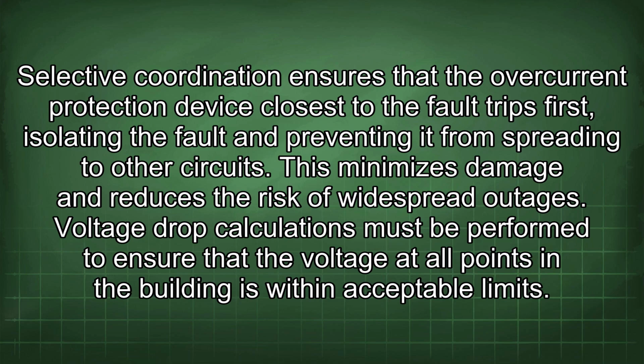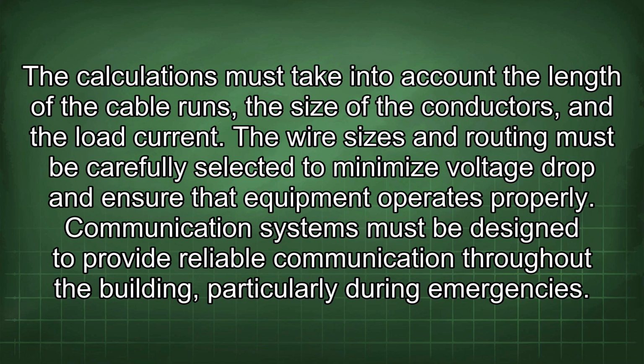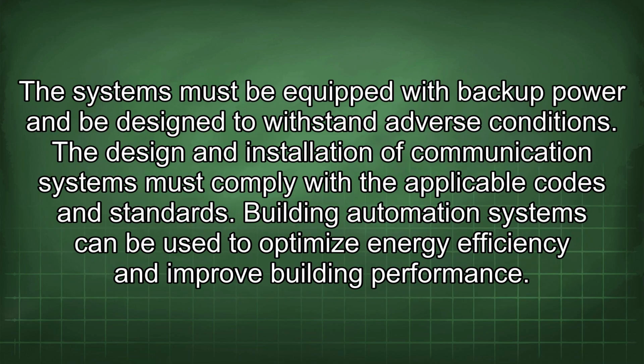Voltage drop calculations must be performed to ensure that the voltage at all points in the building is within acceptable limits. The calculations must take into account the length of the cable runs, the size of the conductors, and the load current. The wire sizes and routing must be carefully selected to minimize voltage drop and ensure that equipment operates properly. Communication systems must be designed to provide reliable communication throughout the building, particularly during emergencies. The systems must be equipped with backup power and be designed to withstand adverse conditions. The design and installation of communication systems must comply with the applicable codes and standards.